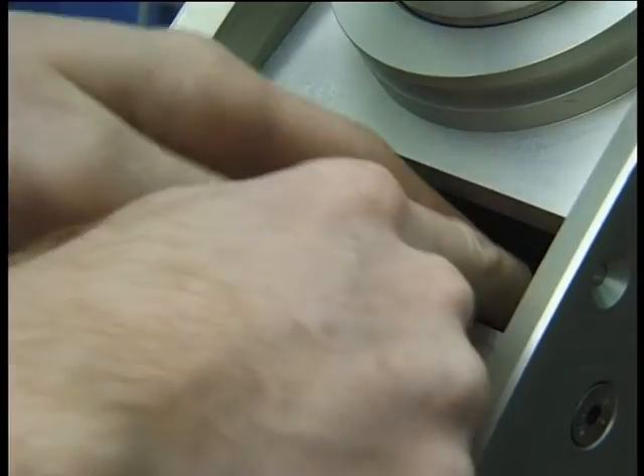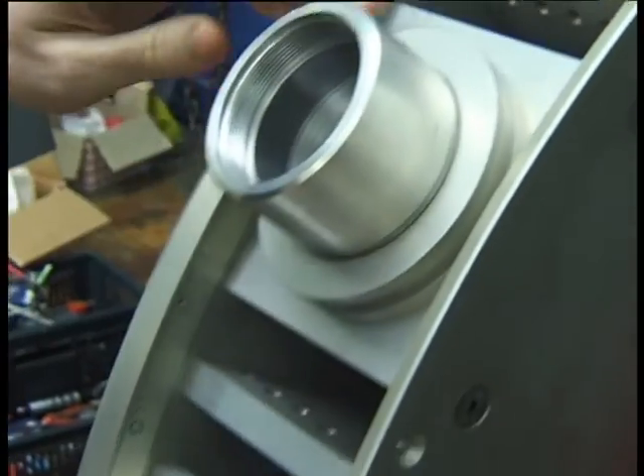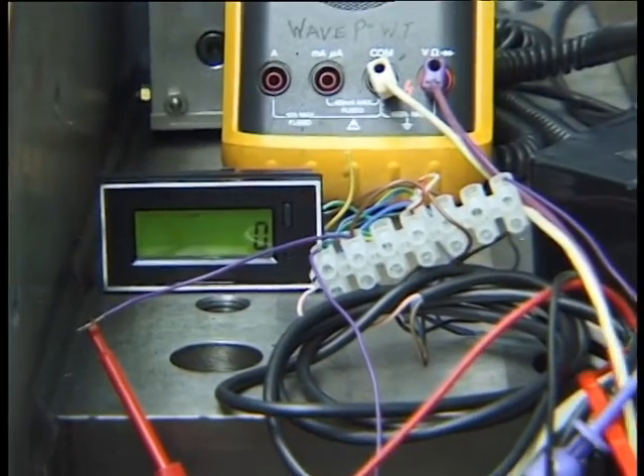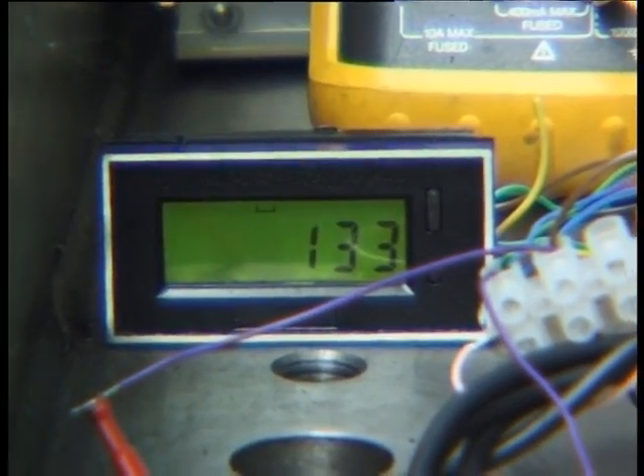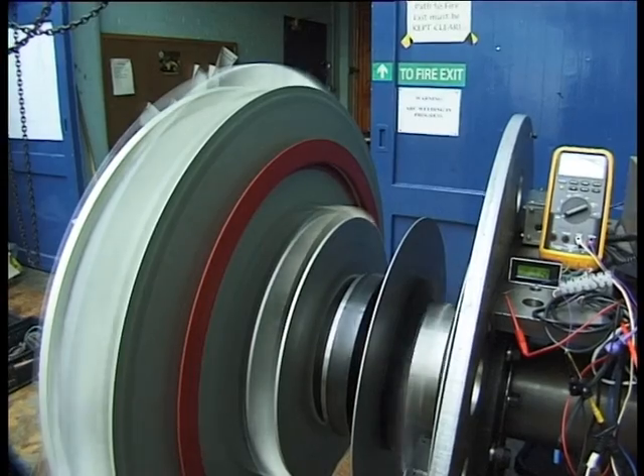For the first spin tests, we fitted temporary dummy spars in place of the turbine blades. These screws and washers are correction weights for the out-of-balance forces on the turbine hub. We spun it at around 500 rpm, and measured the vibrations with a sensitive accelerometer.